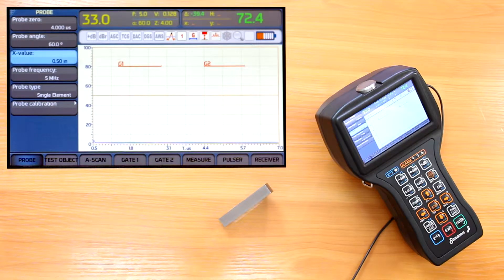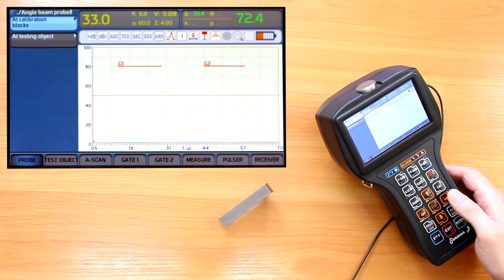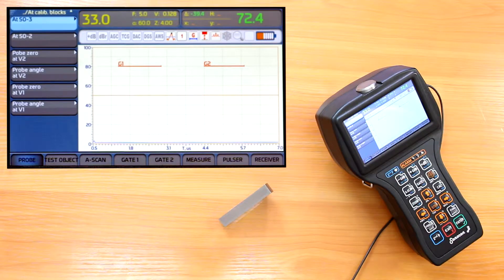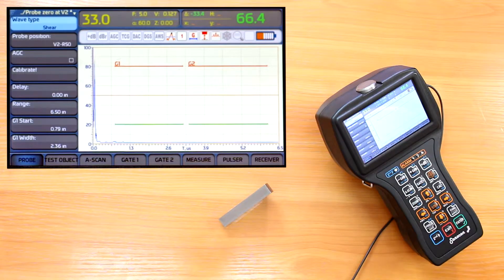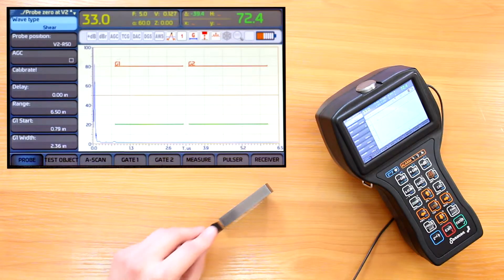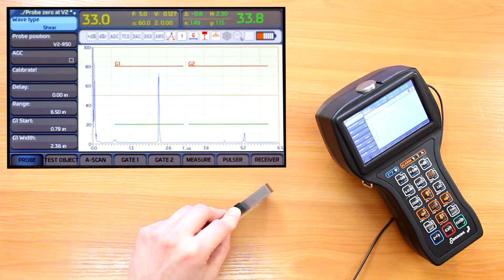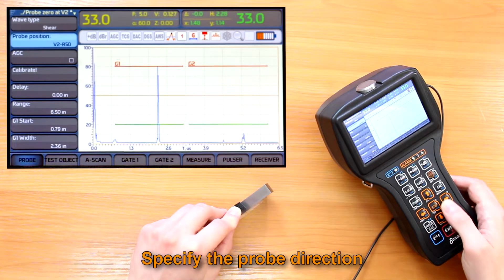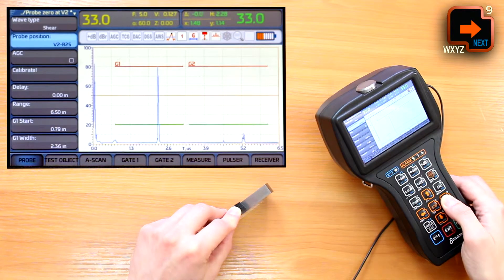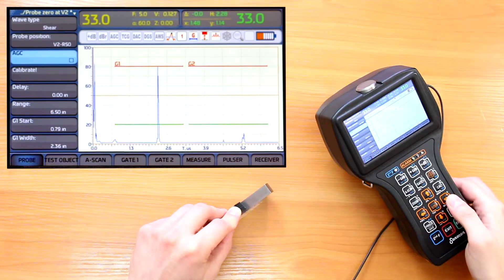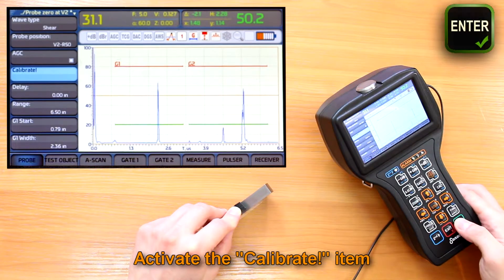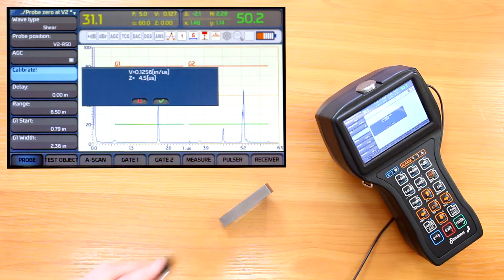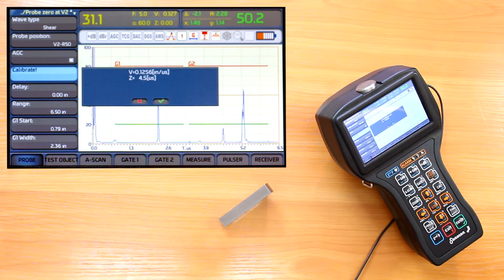I enter the calibration main menu with the calibration button and choose 'At calib. blocks' then 'Probe zero at V2'. I again find and maximize the same echoes. In the probe position item I specify the probe direction to R25 or R50 — R50 in this case. I toggle AGC on to equalize echo amplitudes and activate the calibrate button. The device will show the calculated values of probe zero and sound velocity. We confirm with the enter button.